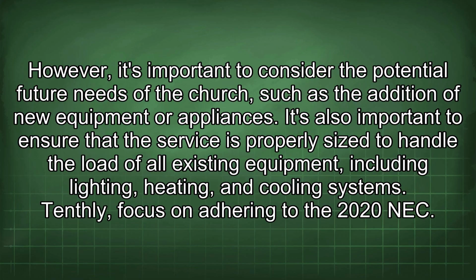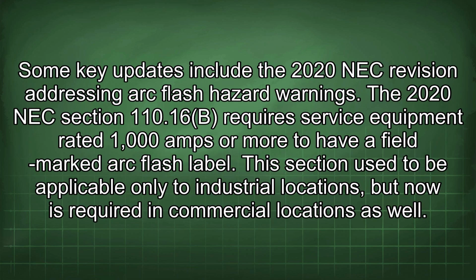Tenthly, focus on adhering to the 2020 NEC. Some key updates include the 2020 NEC revision addressing arc flash hazard warnings. The 2020 NEC Section 110.16(B) requires service equipment rated 1000 amps or more to have a field-marked arc flash label. This section used to be applicable only to industrial locations, but now is required in commercial locations as well.